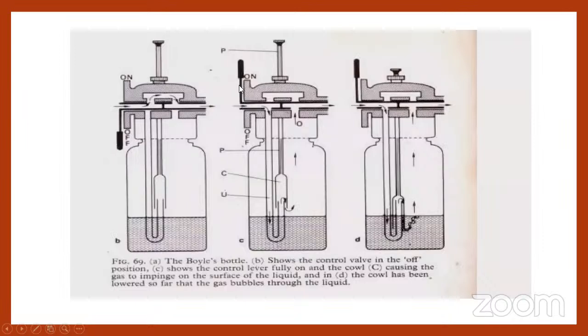When we keep it in the open position, the mechanical lever will be reversed. So the fresh gas which enters the vaporizer will pass through the U tube that is present in the Boyle's vaporizer. Whenever it comes in contact with the liquid anesthetic, it gets vaporized, and this flow of fresh gas on the liquid anesthetic will mix with the vapor and be delivered to the patient. So this is the basic principle of Boyle's bottle vaporizer.